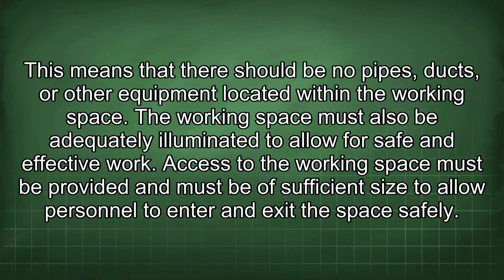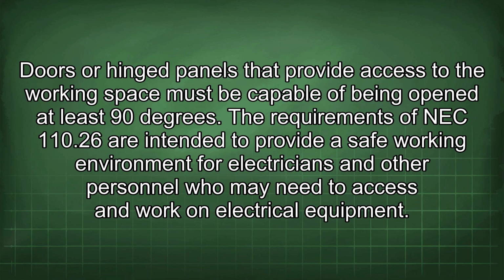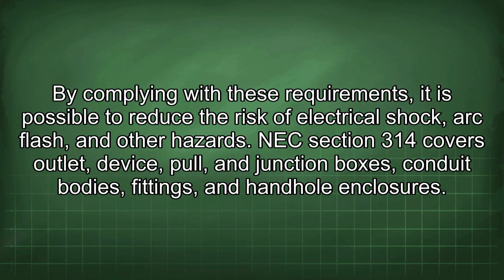The working space must also be adequately illuminated to allow for safe and effective work. Access to the working space must be provided and must be of sufficient size to allow personnel to enter and exit the space safely. Doors or hinged panels that provide access to the working space must be capable of being opened at least 90 degrees. The requirements of NEC 110.26 are intended to provide a safe working environment for electricians and other personnel who may need to access and work on electrical equipment. By complying with these requirements, it is possible to reduce the risk of electrical shock, arc flash, and other hazards.